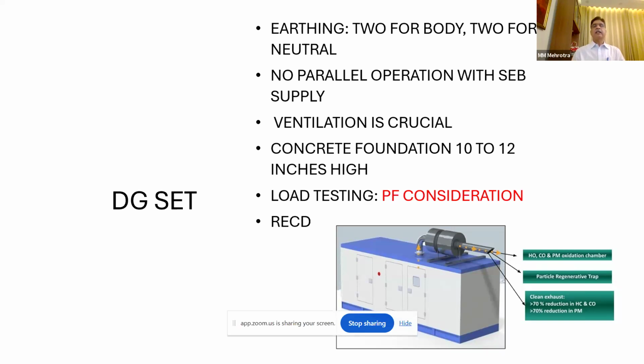When it is a machine, there will always be four earthings: two for body and two for neutral. Then there is the panel. Inside the LT panel, which you saw in the previous slide, there will not be any earthing connected to its neutral. There will be only two earthings connected to the body of the panel. It is not a machine. It is only distribution. In the same way, a transformer will also have two for body, two for neutral.